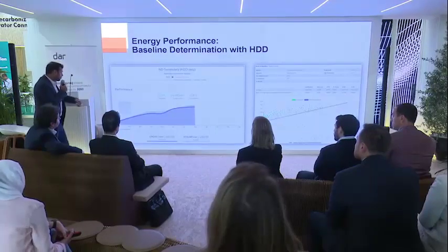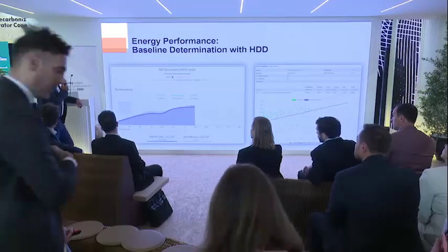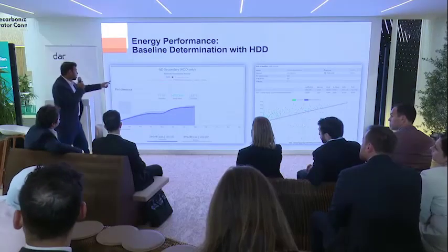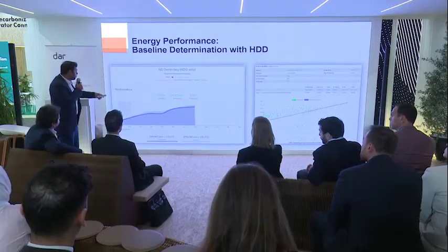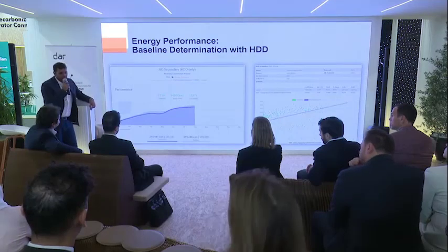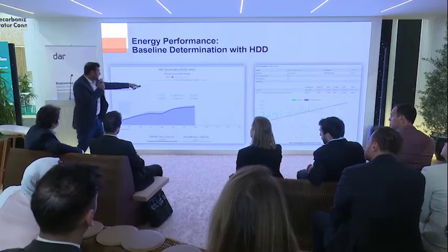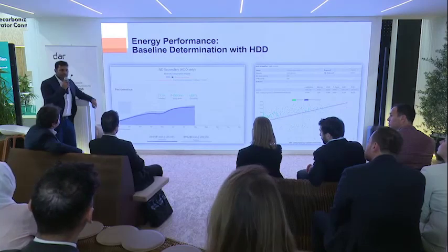Again, an example. You're looking at a school district in Vancouver, actually, and what you have here is an analysis done with electricity. So that's electricity consumption analysis. You're looking at a baseline and then the actual consumption. The baseline is in the green here. That's about 319 megawatt hours. You have an actual consumption that's shown as less than your baseline. And in this case, that's about $3,000 of savings. This was soon after COVID that this analysis was done.